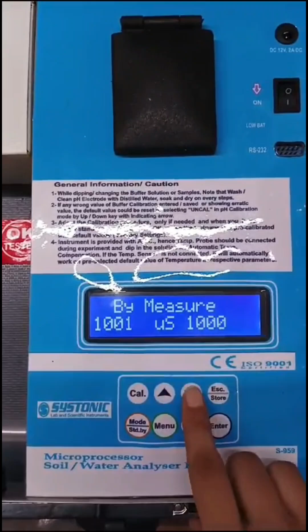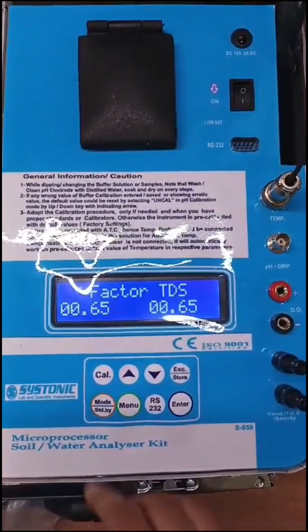and then press enter. To check the conductivity you can go to mode, and from here you can check it. Through this cell you can check TDS and salinity also. Now we will go to cal and to TDS, press enter. We will check the TDS factor, press enter. The factor must be 65, and if it's not, you can change it through these keys. After that press enter, and you can check it by going to mode, and you can change the parameter.